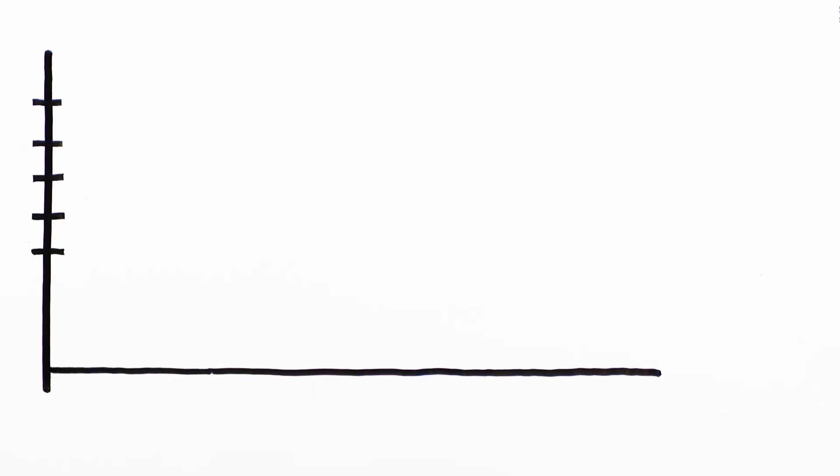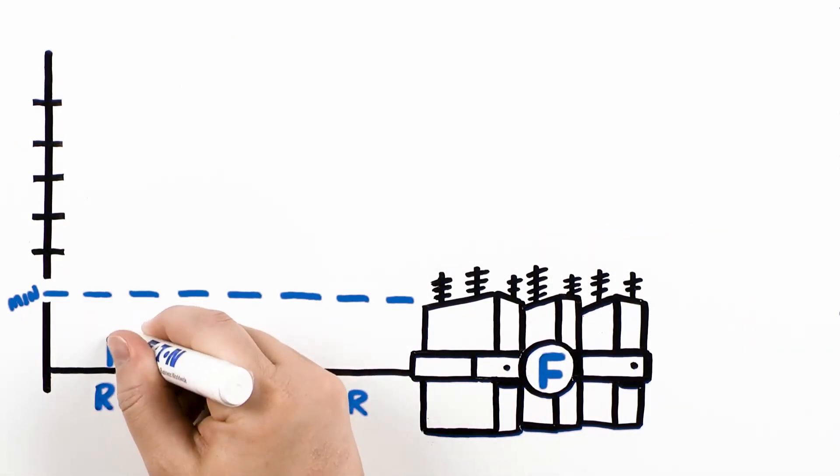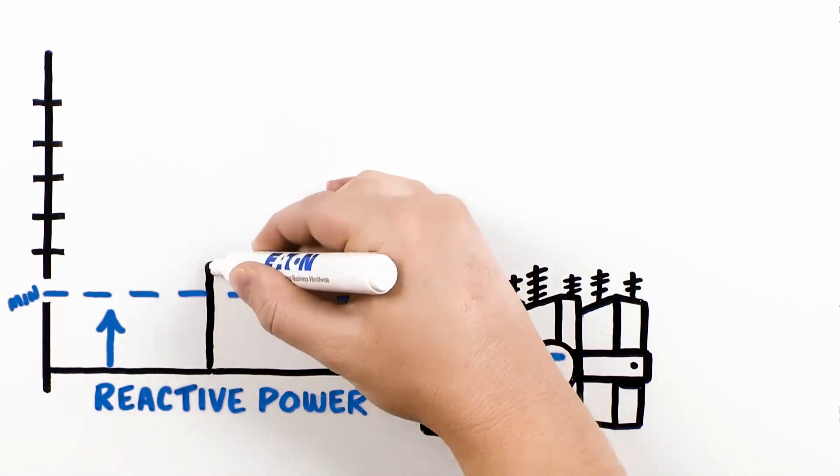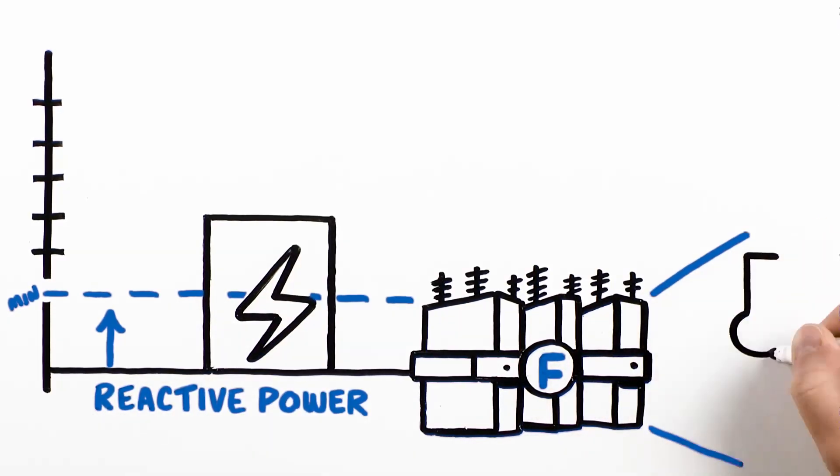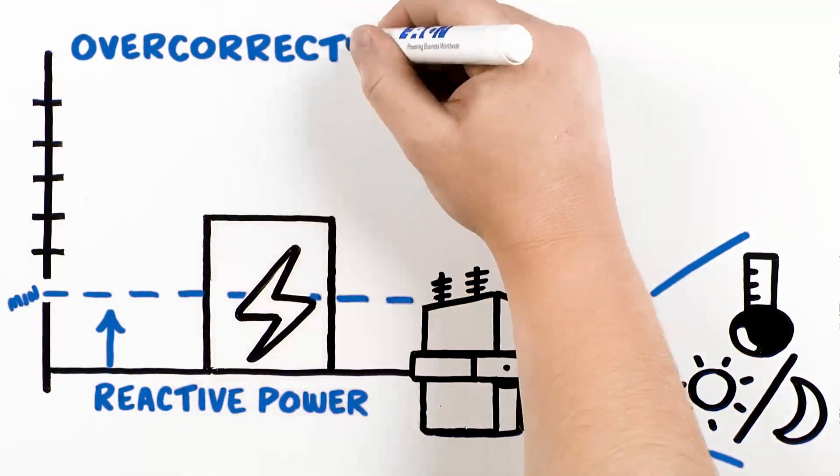Fixed banks ensure that your system consistently has the minimum amount of reactive power needed to perform at lowest load. However, as loads can vary based on the type of equipment on the system and usage, as well as factors such as temperature, time of day and season, it is vital to integrate controls that can prevent overcorrection.